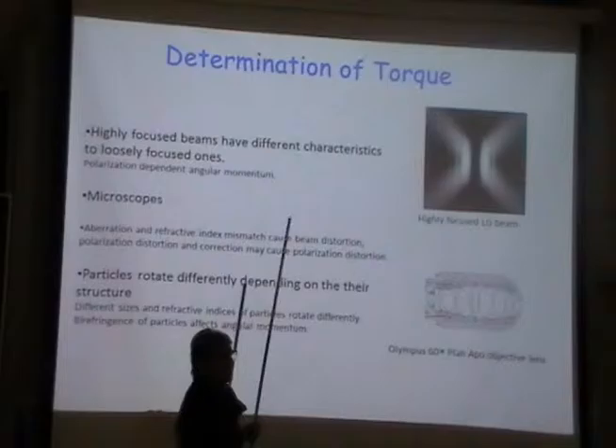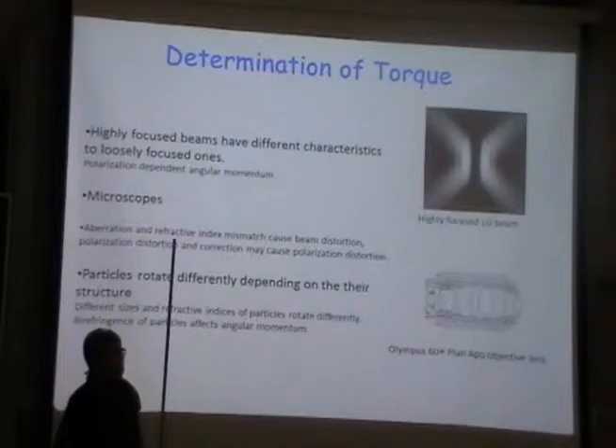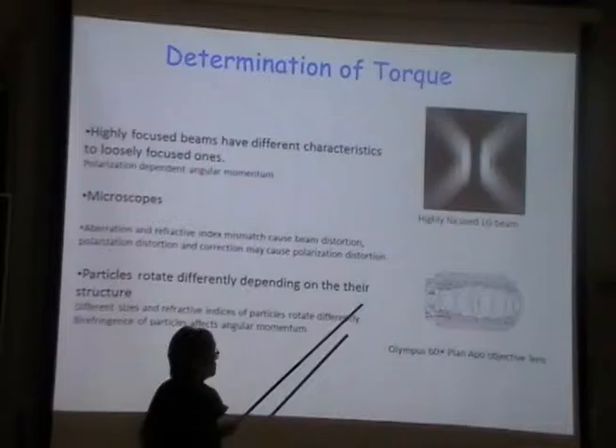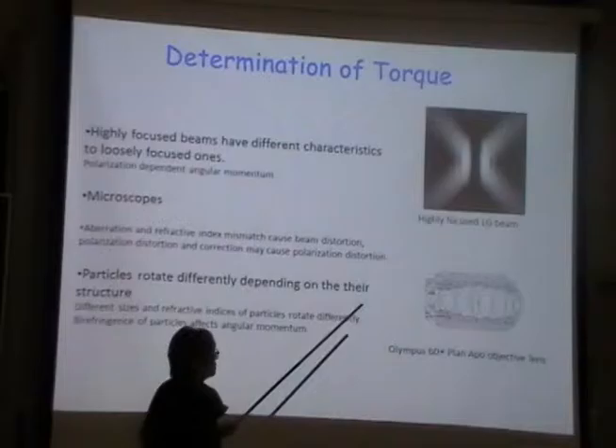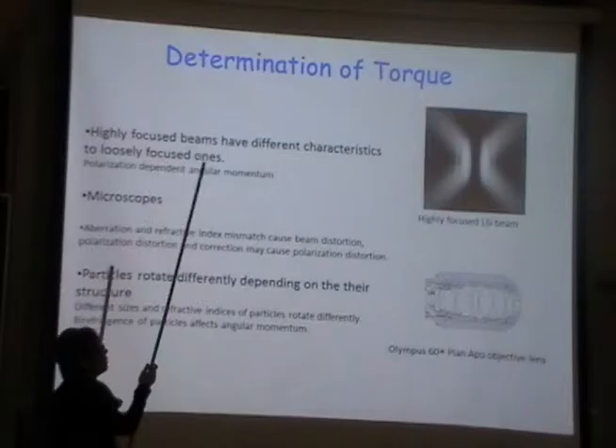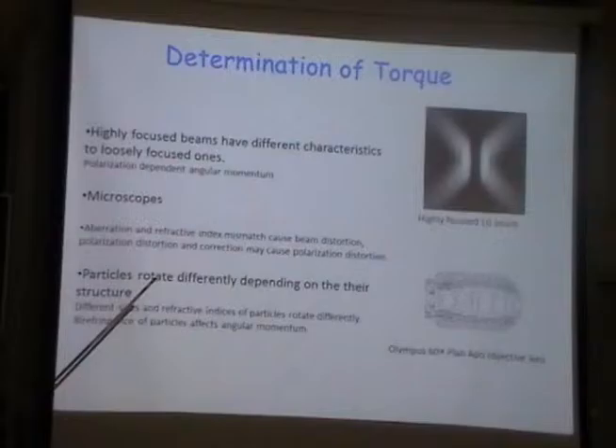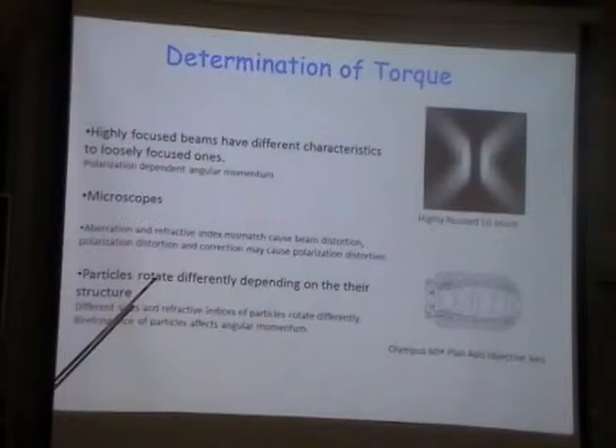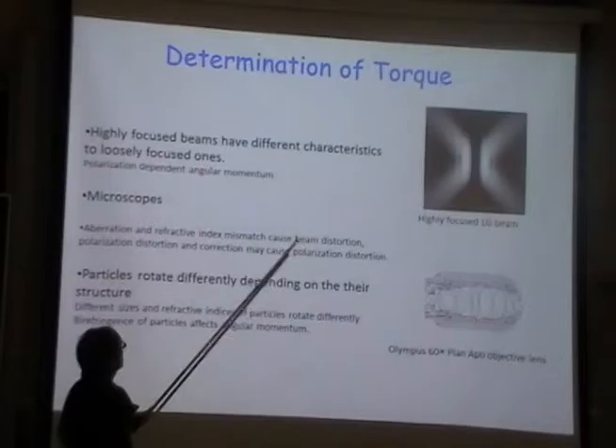A microscope objective is very difficult to control as far as aberrations go. You can pay a lot of money to get an objective corrected for most things, but that objective is only made to work at a certain focal plane. If you are not doing that, you will be introducing aberrations. So, aberrations and refractive index mismatches cause beam distortions, and polarisation correction may cause polarisation distortion as well.